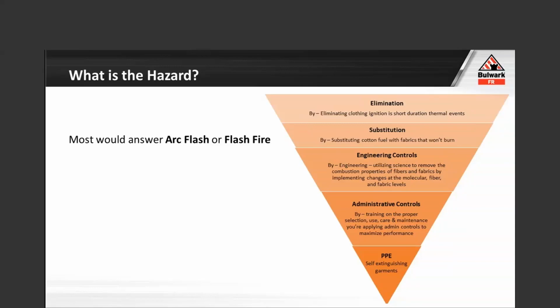We're looking to mitigate injuries. So even if we had an unclothed worker exposed to arc flash and flash fire, we're only typically getting a small percentage of that body exposed, typically 50% or less, which ultimately is not going to result in fatality. So when we look at what the real hazard is, what are we really preventing against?